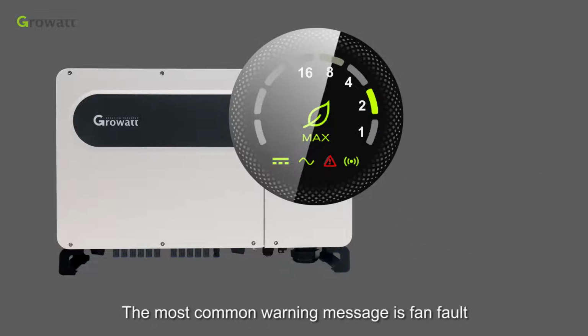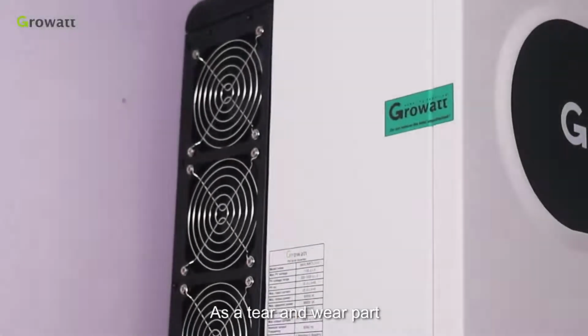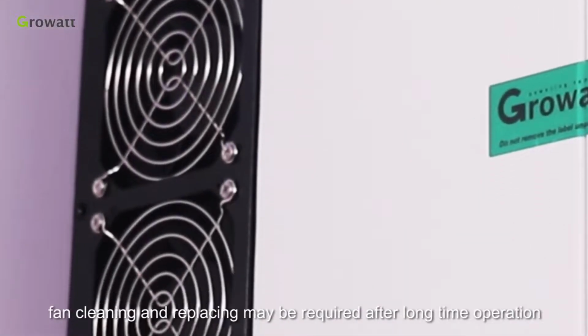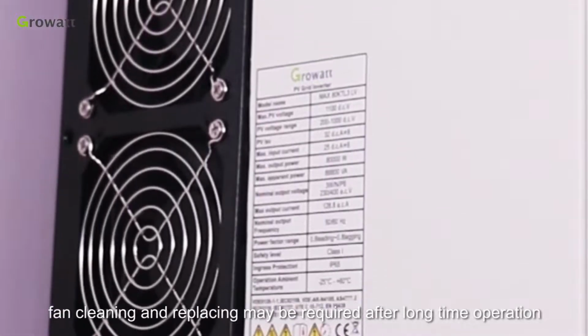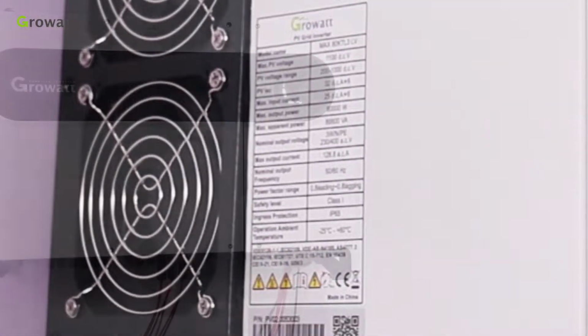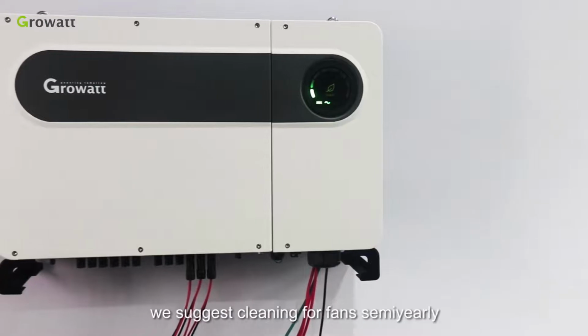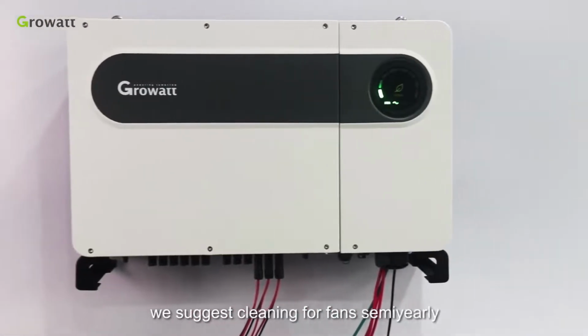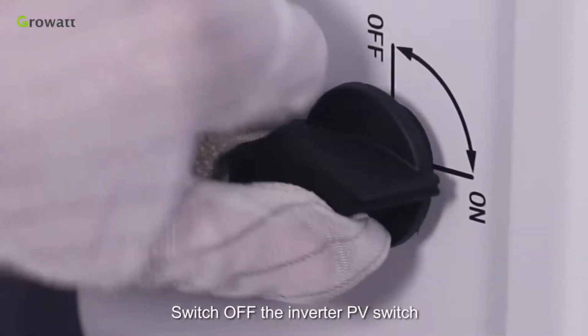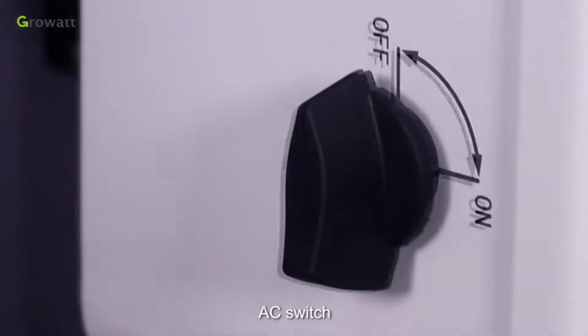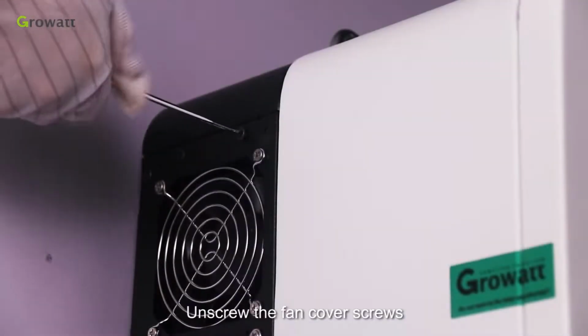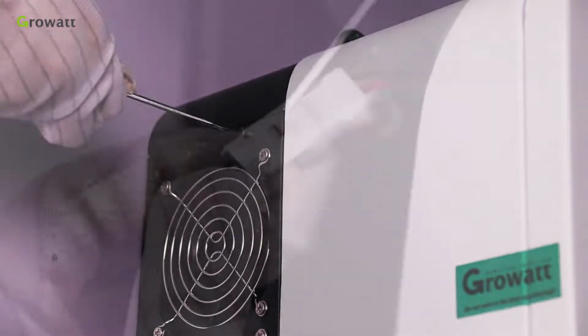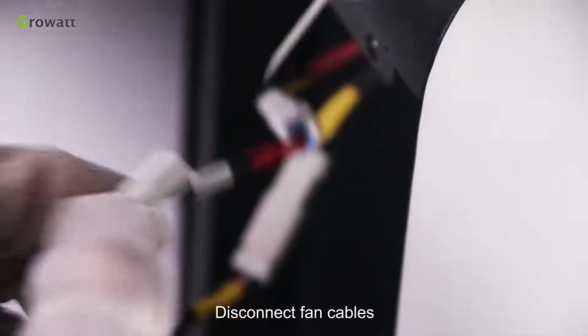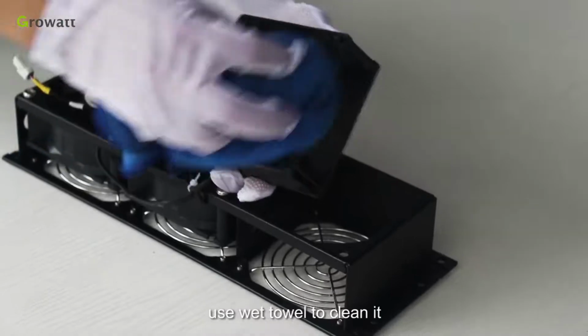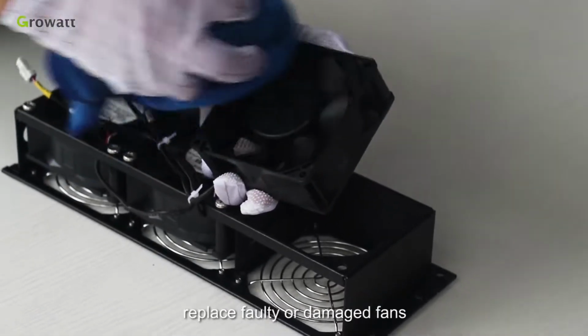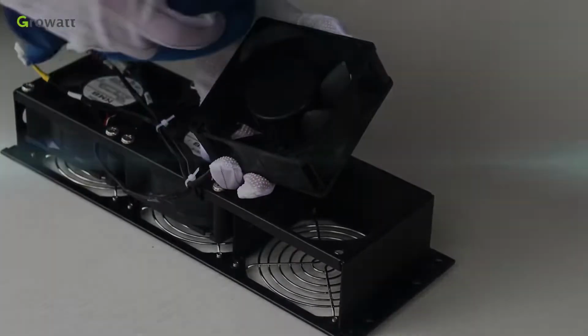The most common warning message is fan fault. As a wear and tear part, fan cleaning and replacing may be required after a long time of operation. For outdoor installations, we suggest cleaning the fans semi-yearly. Switch off the inverter PV switch and AC switch. Unscrew the fan cover screws. Disconnect the fan cables. Take off the fans. Use a wet towel to clean them. Replace faulty or damaged fans.